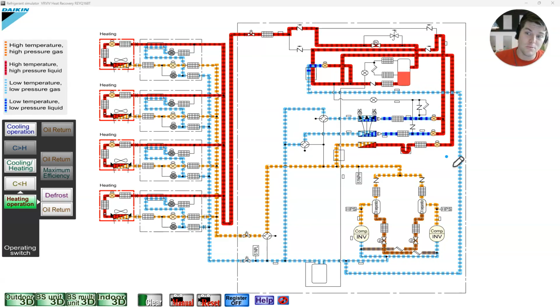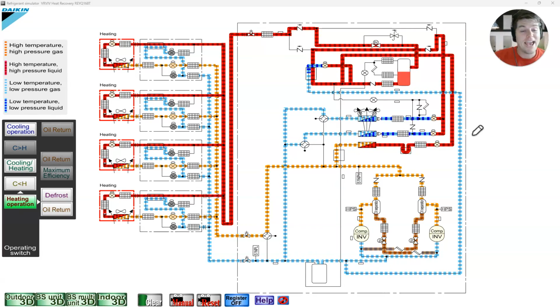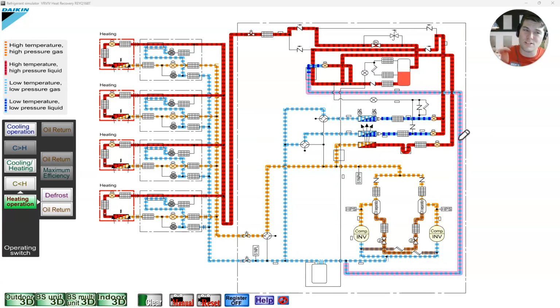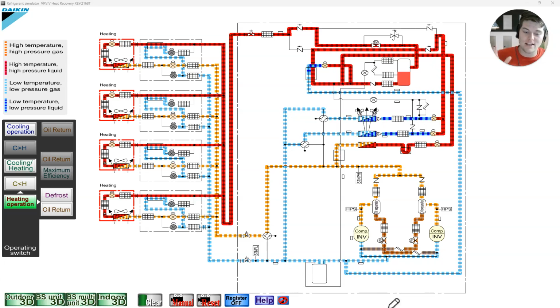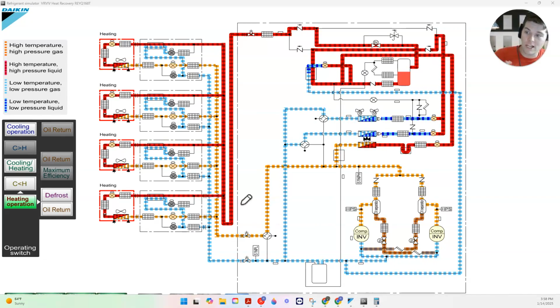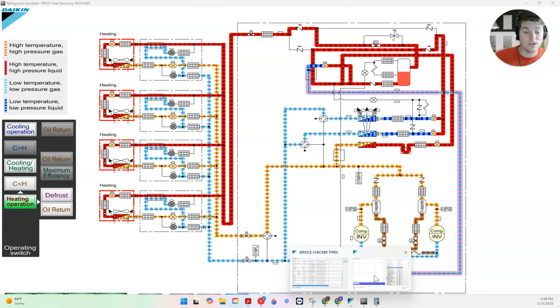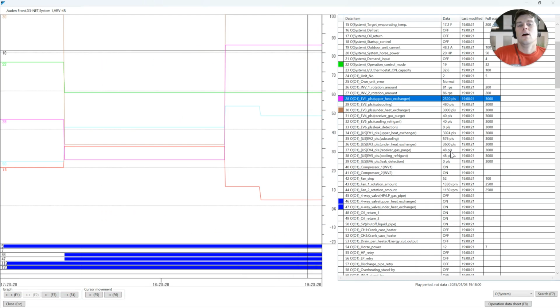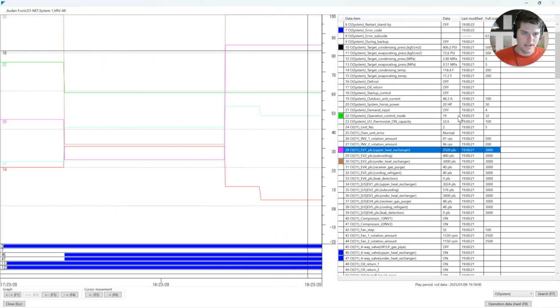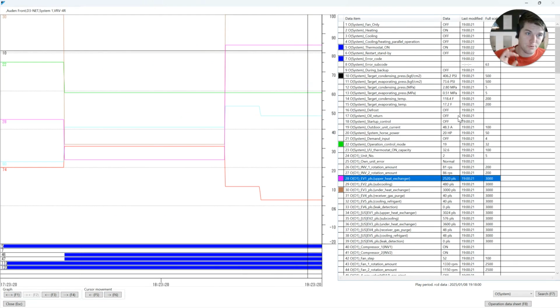And I have 0 subcooling on my liquid line at this point in time, and it actually stays that way. It's maybe 2, it's maybe 3. It's that quality of liquid over time that tells us and seals the deal here to show us that it's really a problem. Whew, man, I need a cigarette after this one, but I don't smoke. So this is discharge superheat, suction superheat, subcooling, how you use it in Service Checker to diagnose a heating problem.